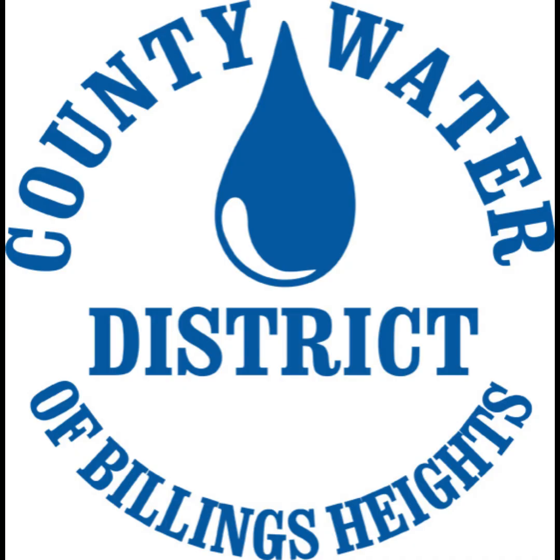So now I'll go over the problem definition. The Lake Hills pressure zone has trouble maintaining pressures during high demand events. We use KY pipe to model the hydraulics. After 2 years, pressures during the existing peak day demand of 3,000 GPM while fighting a fire of 1,500 GPM will fall below the DEQ minimum of 20 PSI. And for the 20-year design year, if no changes are implemented to the existing system, nearly all pressures in the Lake Hills pressure zone are negative during the peak day demand of 4,800 GPM while fighting a fire.